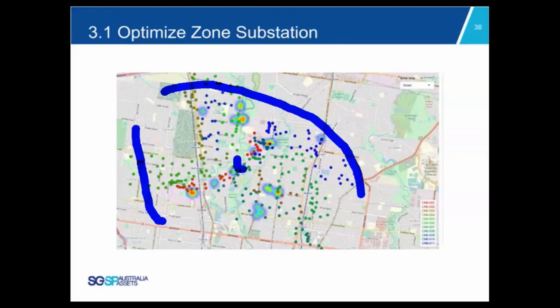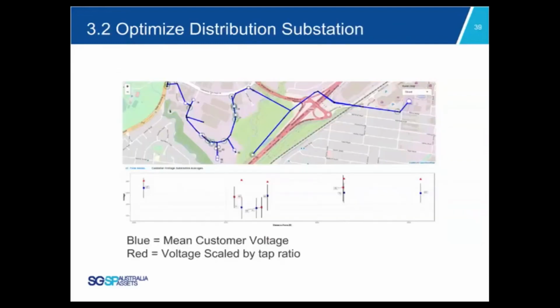And you can see here, the voltage problematic location with high density of events. Based on this location, how to choose which substation tap setting needs to be changed in our HV feeder will be the next question. So let's zoom in into the potential voltage problematic location.